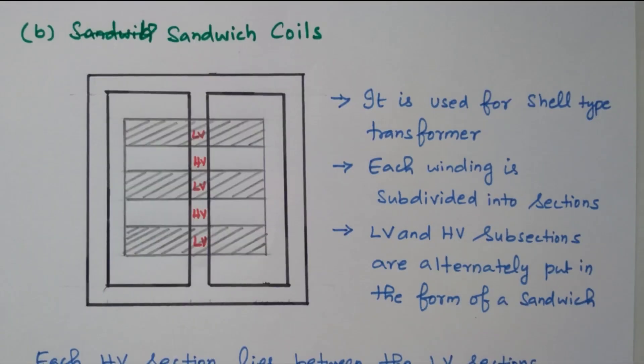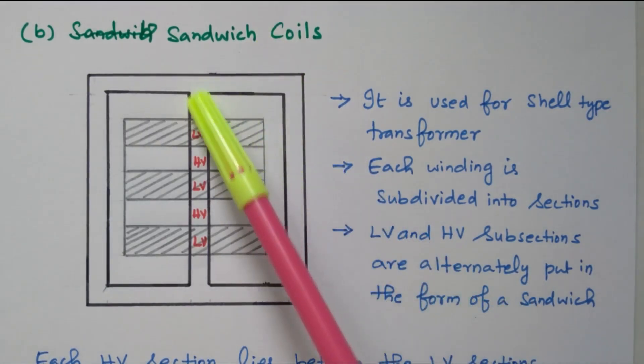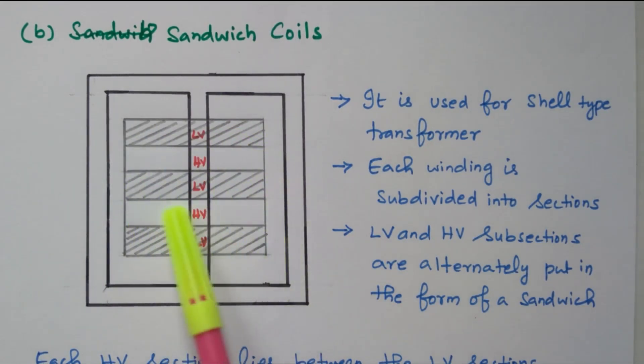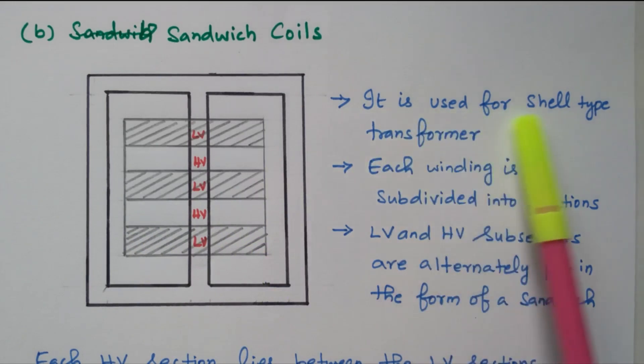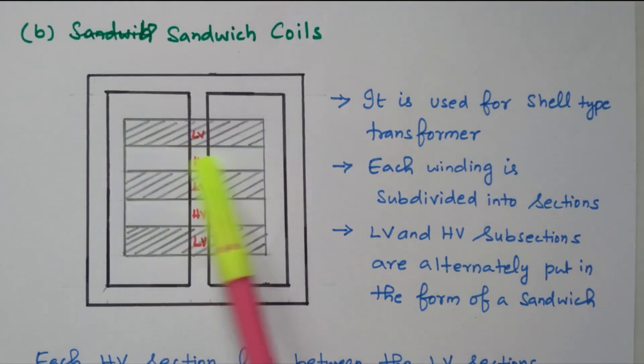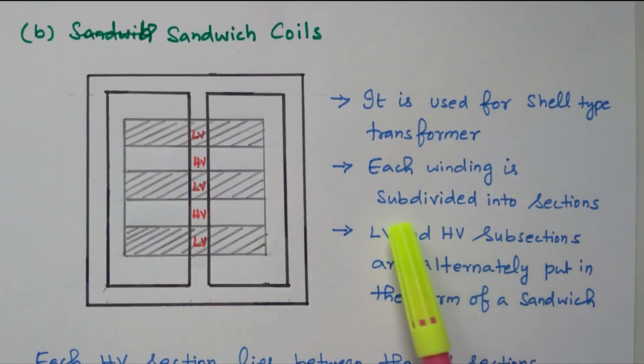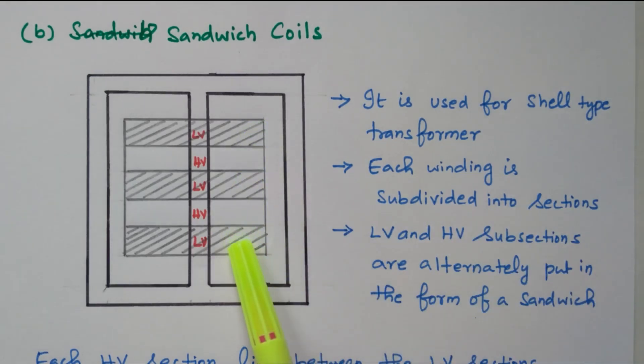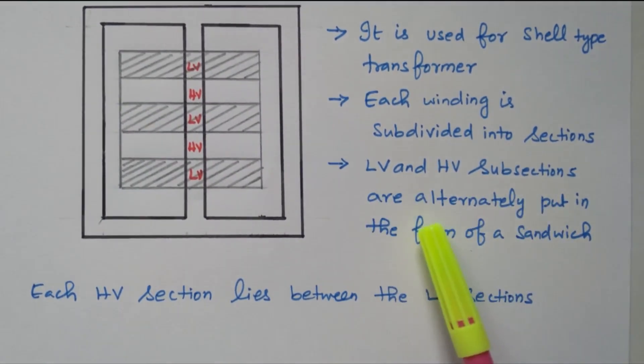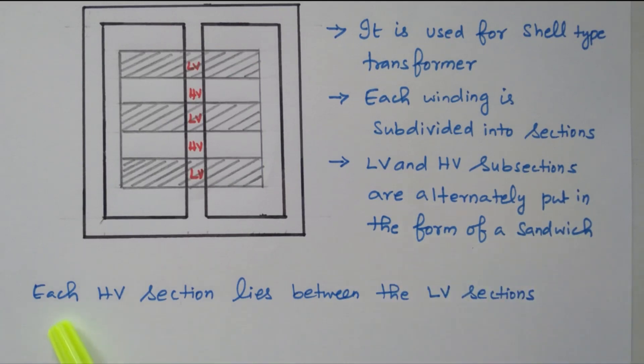In the sandwich type, at the center limb the windings are alternated: first low voltage, then high voltage, then low voltage, then high voltage, then low voltage — like a sandwich. It is not overlapped. This is used for the shell type transformer. The shaded portions are the low voltage windings and the normal portions are the high voltage windings. Each winding is subdivided into sections, and the LV and HV subsections are alternatively arranged. Each high voltage section lies between the low voltage sections.